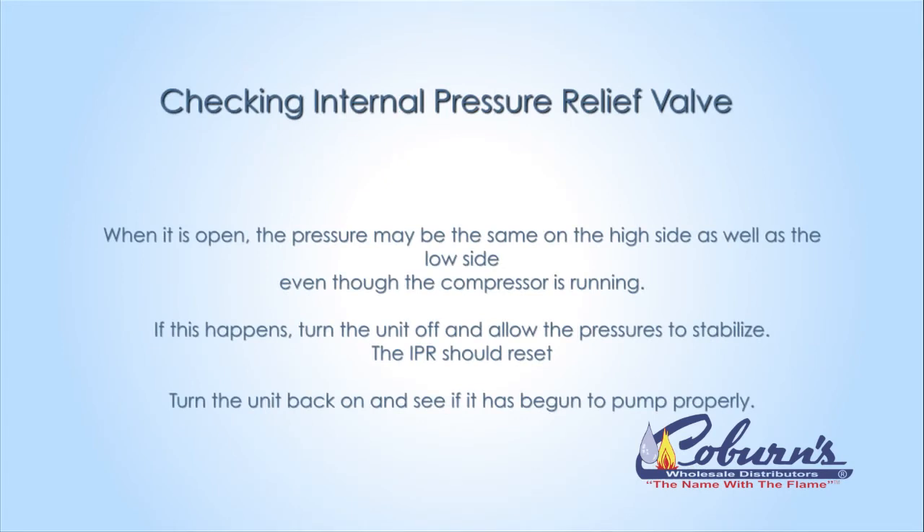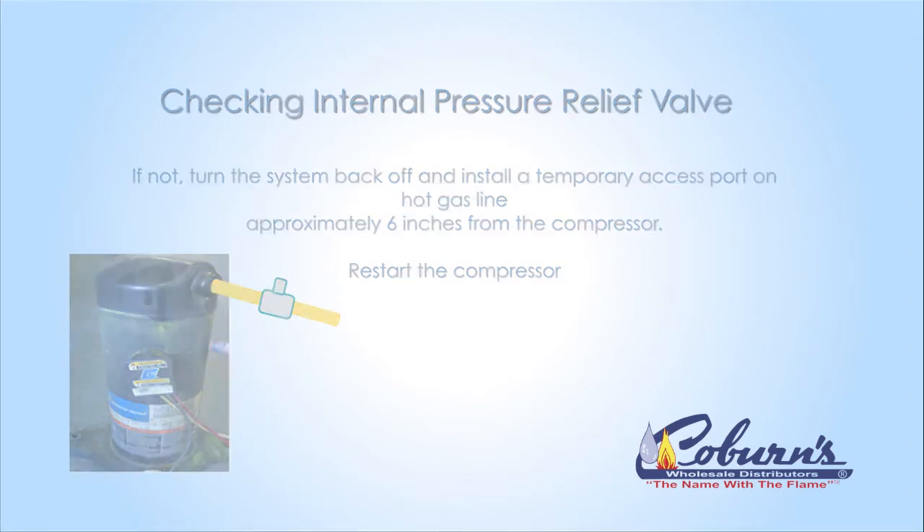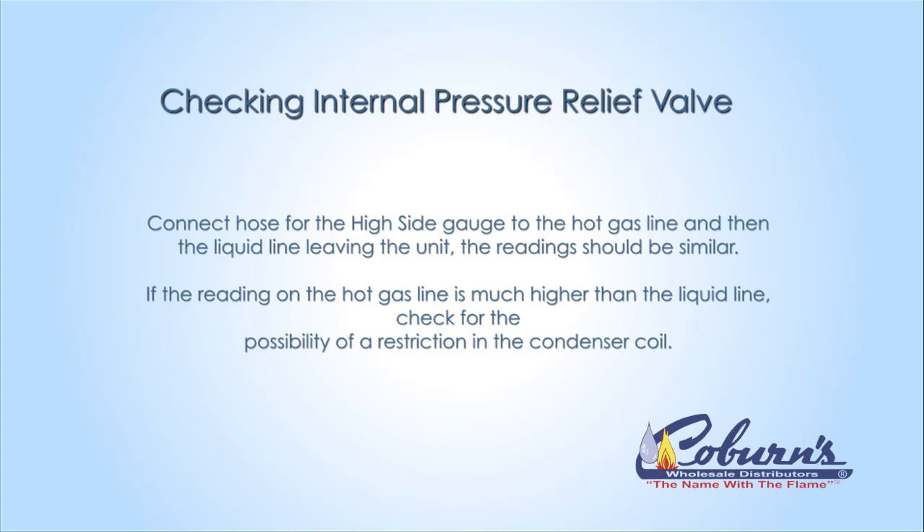If the IPR opens, disconnect the power to allow the compressor to shut off and equalize — the IPR will reset. If the IPR doesn't reset, turn the system off once again. We're going to put a temporary access port about 6 inches away from the compressor on the hot gas line. If the pressure taken at that access valve is equal to the pressure leaving the condenser, then the IPR is popped open and won't reset. If the pressure is much higher on the hot gas line, this means you may have a restriction inside the condenser.